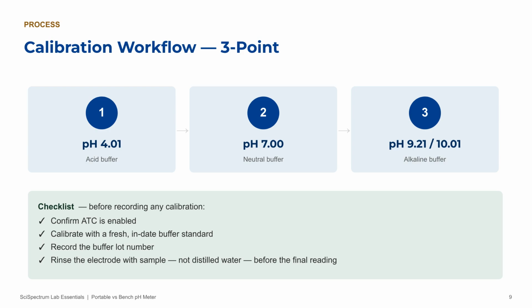A benchtop gets calibrated under stable bench conditions, usually once a shift. A portable often gets calibrated out in the field, where the ambient temperature is a lot less predictable. Before you calibrate either one, run through this checklist. Confirm ATC is enabled. Use a fresh in-date buffer standard. Record the buffer lot number, and rinse the electrode with sample, not distilled water, before that final reading.